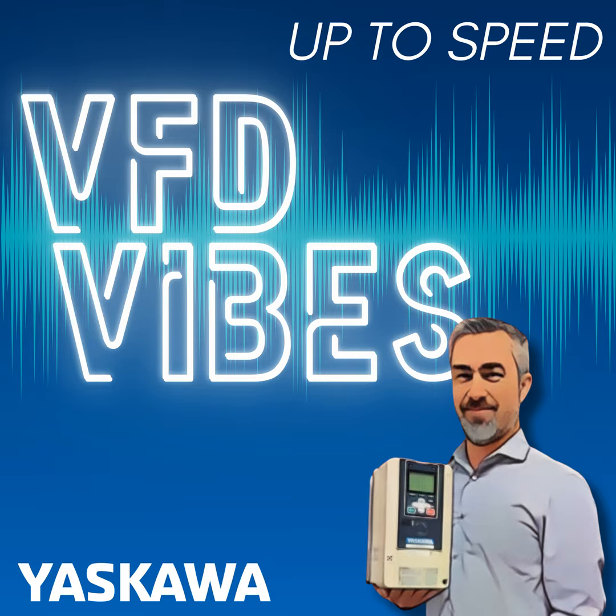Now, type 12 is also designed for indoor, but it has a higher degree of protection. Think dirty mechanical room. Maybe you have some chilled water pipes running overhead that sweat from time to time because there's humidity changing. Maybe the maintenance personnel leave doors open because it's not air conditioned. In the summertime, it's hot in there. We have dripping pipes. Maybe it's a manufacturing facility.